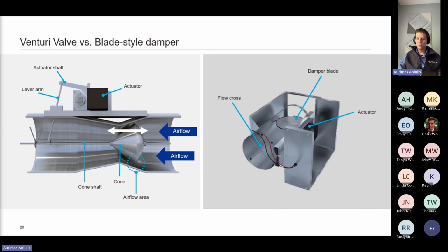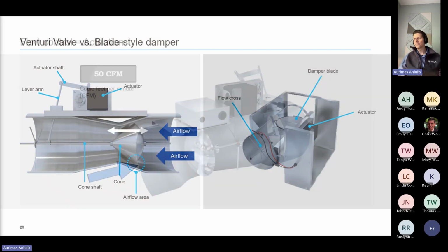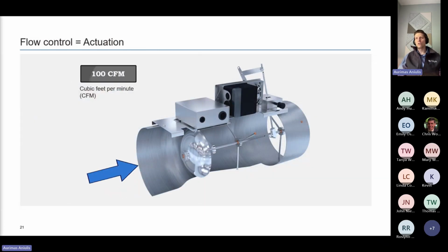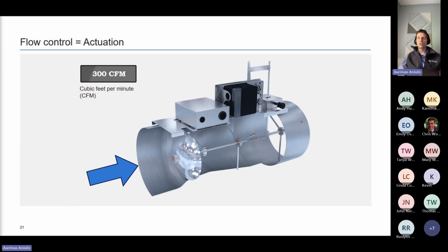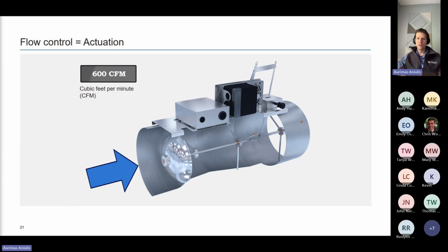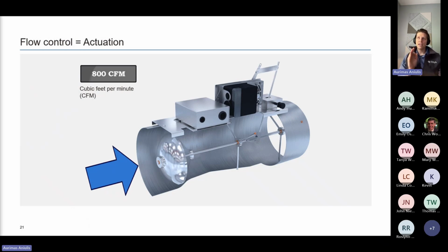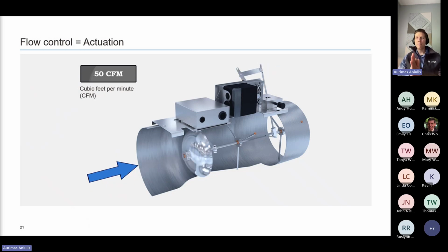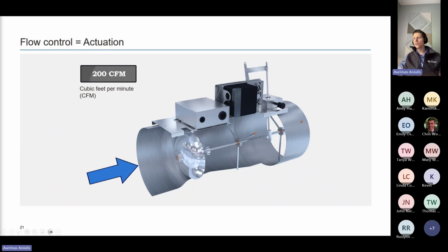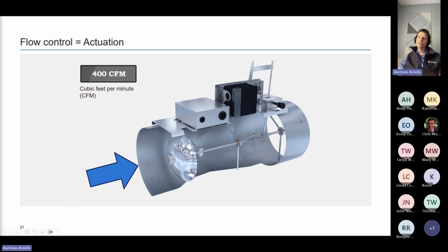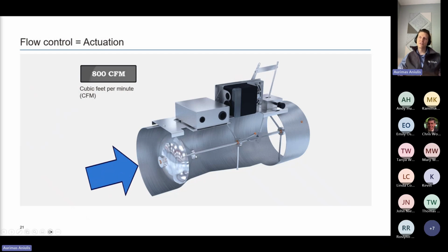As we progress, we're going to take a look at the value and benefit of both of these technologies. So the first one is the Venturi, and it's important to understand the difference between flow control, which is actuation of the device, commanding it to go to a different CFM set point, and then once it's arrived at that CFM set point, how it maintains that CFM set point without any actuator movement. So what you're seeing right here, this black guy, is the actuator. It's modulating the linkage, which is driving the cone shaft and repositioning the cone to a different CFM position.